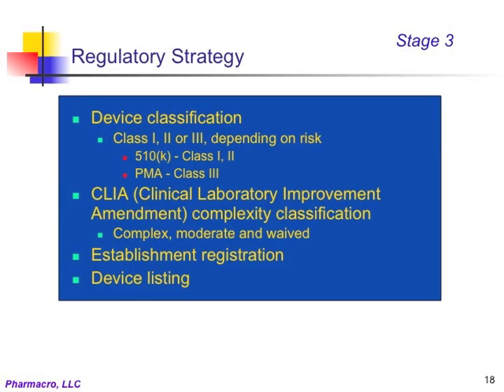The CLIA classification defines the complexity of device based on how it is used. There are three categories: complex, which applies to tests that require a well-trained technician to conduct the test; moderate, which applies to tests that require some training for conducting the test; and waived, which applies to tests that can be conducted without training in a home use environment. This classification determines the type and extent of testing that will need to be conducted to demonstrate safety and effectiveness of the device.